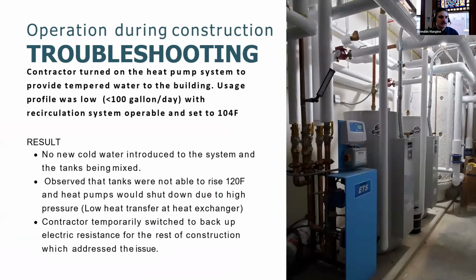Another thing we ran into was during construction, we found that when the load was really low and we had the recirculation system turned on for normal operation in the building, it would churn the water up in the storage tanks and they wouldn't be stratified. And we wouldn't be getting any fresh cold water into the system. So when the heat pumps would call, the tanks would drift below the target set point, but they were completely churned, so it would be pulling tempered water into the cold water inlet. Since these heat pumps are single pass, they wouldn't be getting enough heat transfer across their heat exchanger and would go off on high pressure.